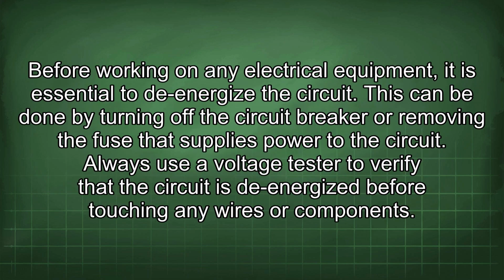Before working on any electrical equipment, it is essential to de-energize the circuit. This can be done by turning off the circuit breaker or removing the fuse that supplies power to the circuit. Always use a voltage tester to verify that the circuit is de-energized before touching any wires or components.